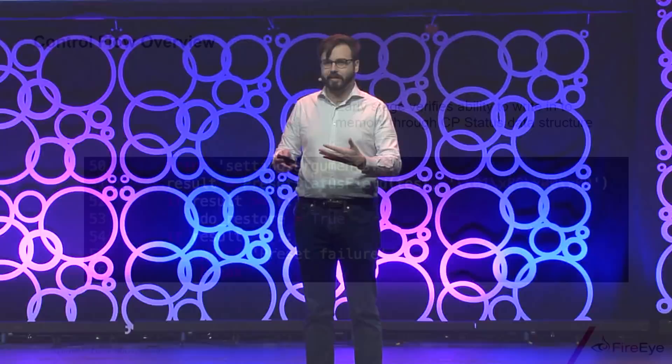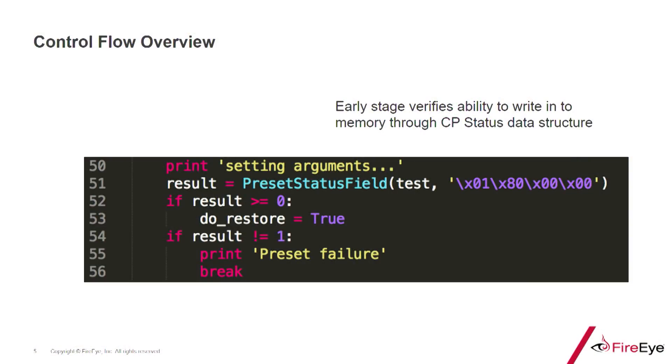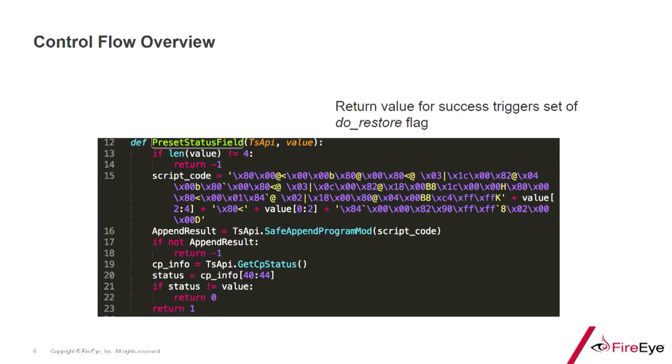At a very early stage, one of the first few lines of the attack script — this is decompiled Python bytecode from Trilog.exe — the malware runs a method called preset_status to set four attacker-controlled bytes in a region of memory corresponding to the CP status data structure. This was likely used as an echo test to verify their ability to read and write memory before delivering the imain.bin memory backdoor. The method inserts shellcode to write those bytes into memory, then attempts to read them back using legitimate TriStation protocol commands to view controller status.